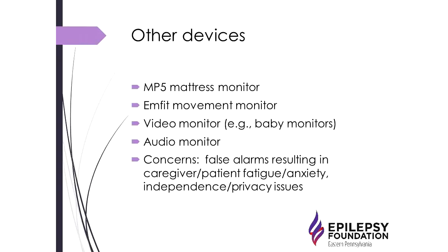There are also mattress monitors for sleep-related seizures. The MP5 mattress monitor underwent a clinical trial and was effective in detecting about 60% of convulsive seizures with about 90% specificity — meaning when it alarmed, it was usually a real seizure, though there were false alarms. That's a UK-based company. There's also another device called the Emfit Movement Monitor, also intended for sleep-related seizure detection.